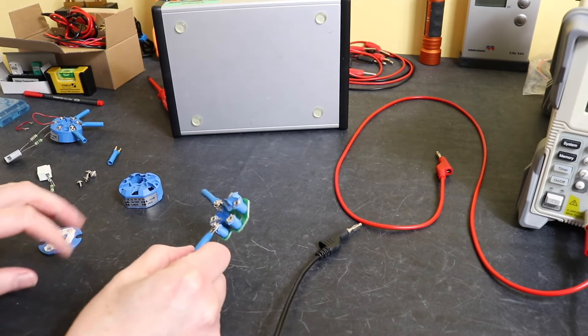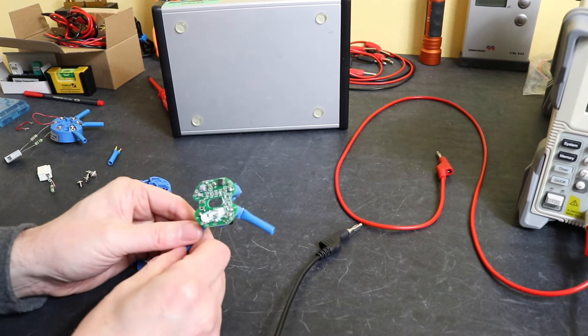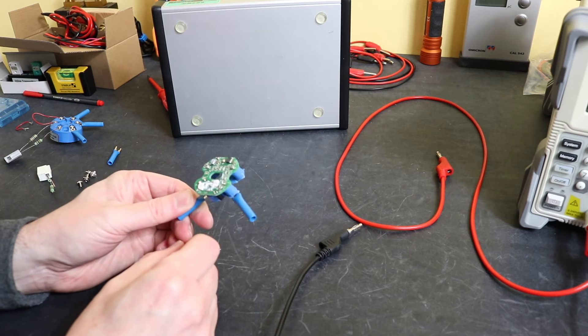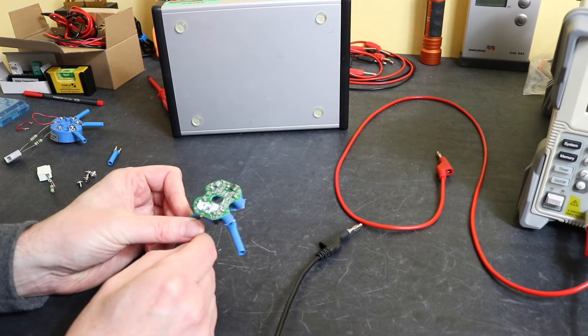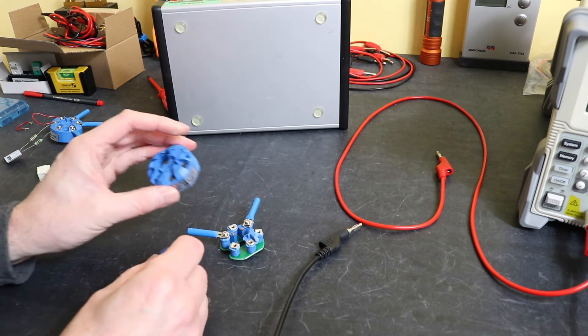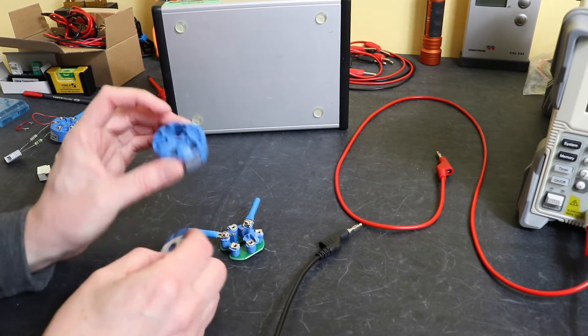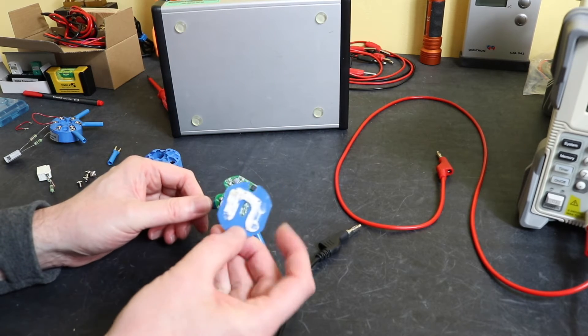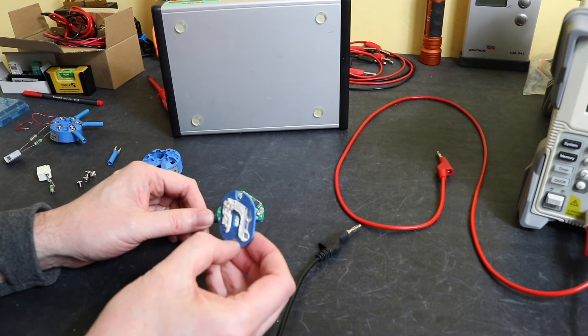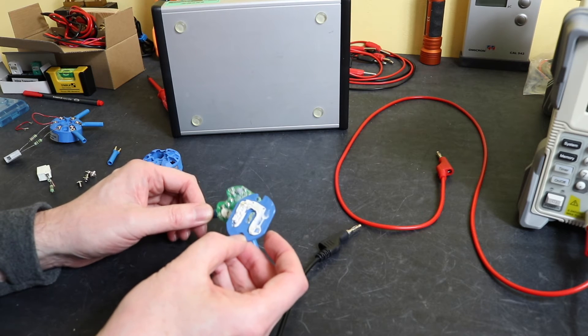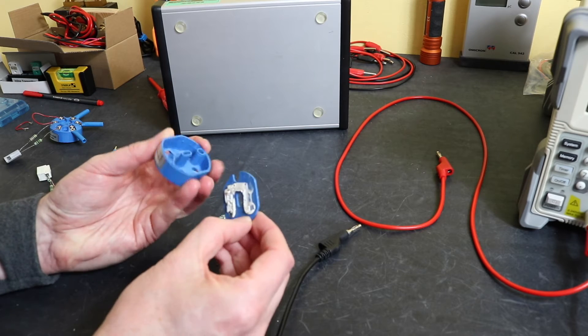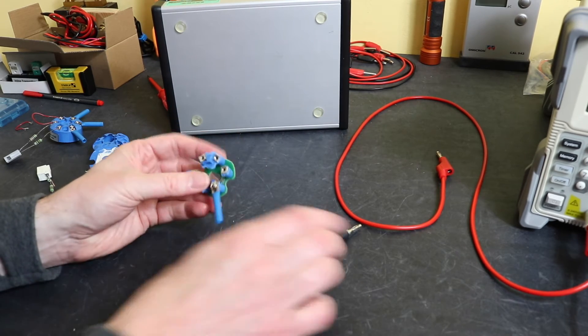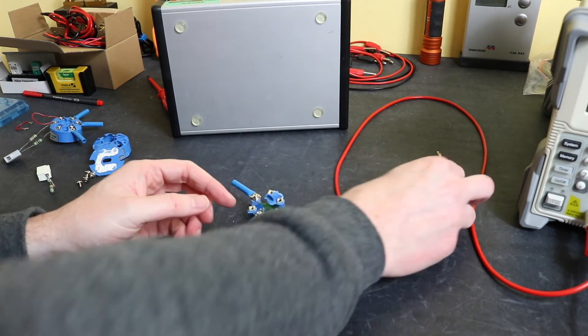So that's the issue that I've got. We'll pack up now and I'll break this unit open and see if we can see anything inside. So we have gained access to the little temperature puck here and it isn't potted, and I guess that gives you another issue doesn't it, that depending on the environment these are installed in, they are obviously susceptible to humidity and moisture ingress and dirt and the like. I was expecting it to be all glued up and not much use, but it gives us a little thing to look at. These are soldered in and like a numbskull I just smacked them out so I've broken the case doing that. The back was just glued on with some silicon kind of substance, so again not much there's no real seal there to prevent any dirt or moisture getting in there.